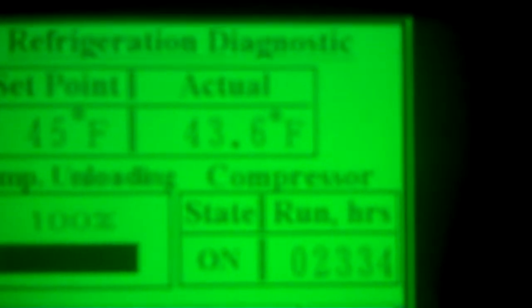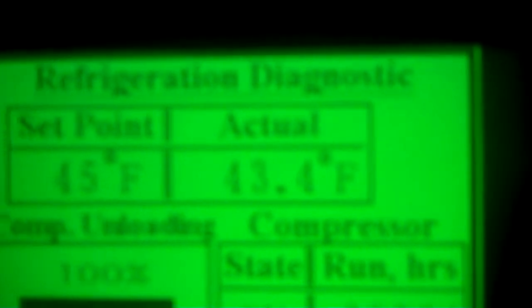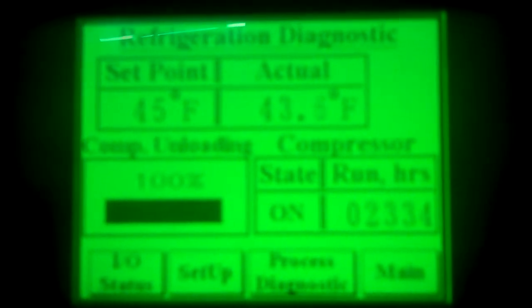That's 100% of the hot gas bypass, or as the screen indicates here, unloading. So I hope you can read that. That's 43.6 F right now. 43.4. So our chilling slowed down quite a bit once we approach set point and we're at that 100% unloading.